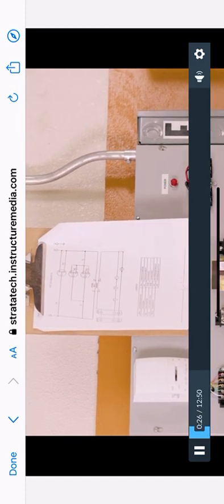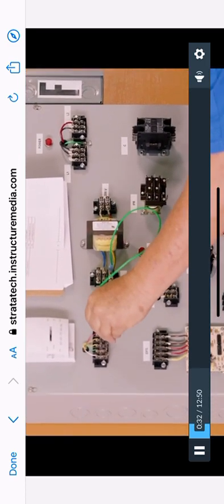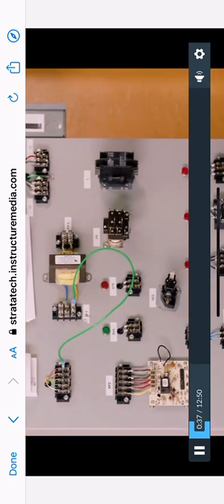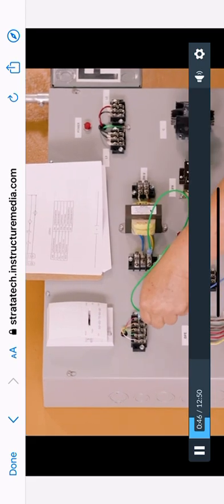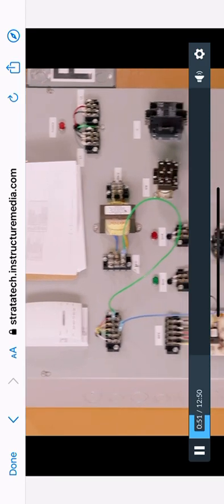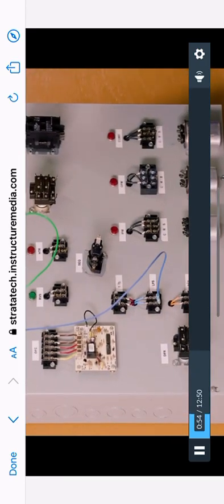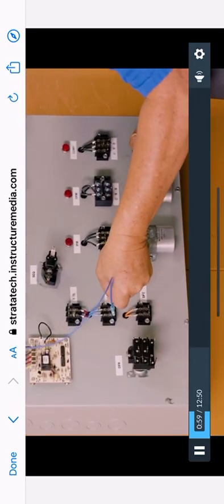So we got our transformer, 24 volts. We're going to run a wire from the 24 volts to the red of the thermostat, which is this wire here. We're going to go from our Y terminal right here to our low pressure switch. So you get your wire and put it on the yellow wire, put it on the low pressure switch, this is right here. You're going to come out of your low pressure switch and you're going to go to your high pressure switch. So you're going to come out right here and you're going to go up here.